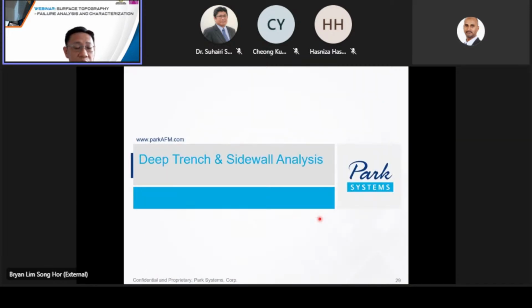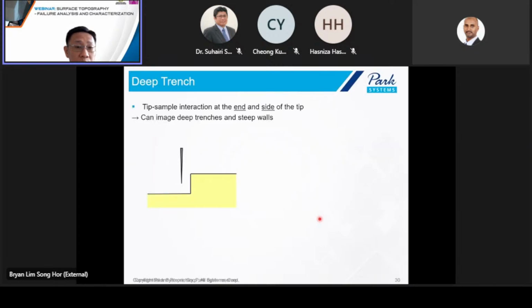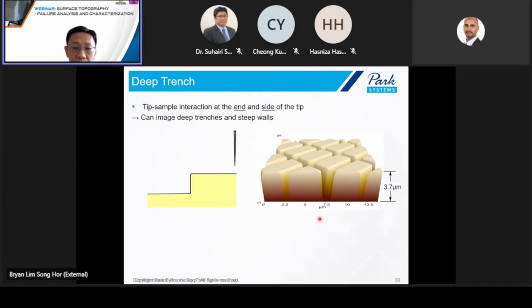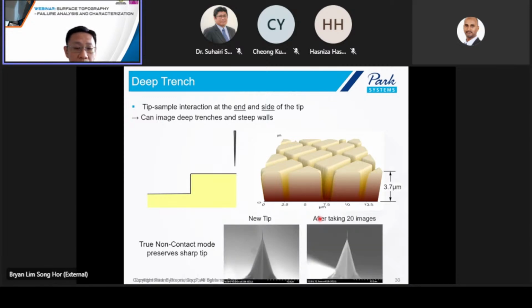Okay, so another mode is called deep trench and sidewall analysis. This is more in the semiconductor industry, where they have very deep and narrow trenches, and with other characterization methods, it's difficult to find the depth, especially when the opening is very, very narrow. So this is the AFM tip, imaging the trench. This is the profile, 3.7 micron depth, and the tip will remain sharp because of our system's non-contact mode.